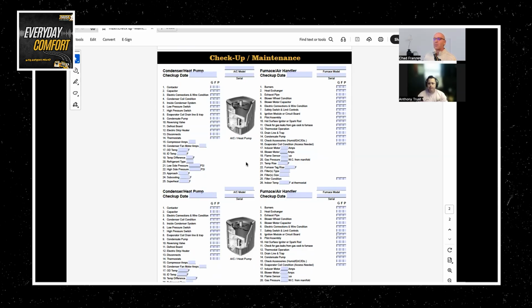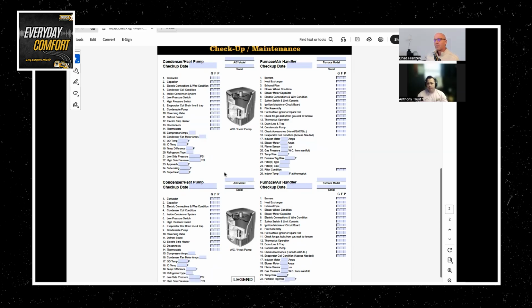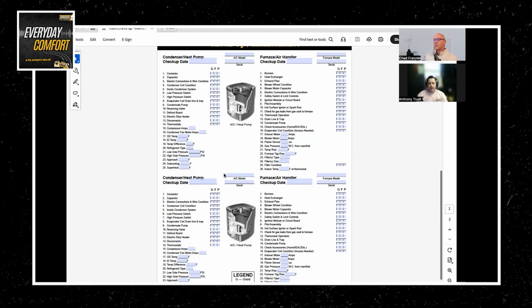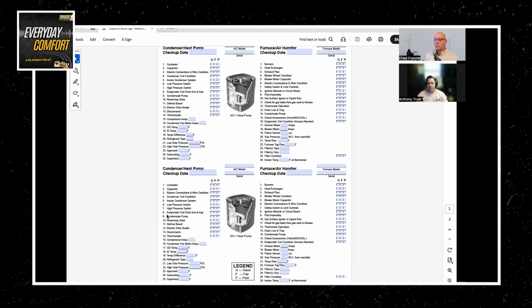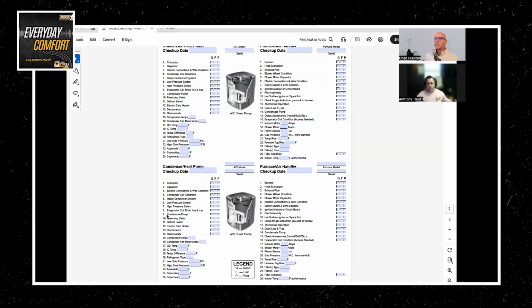Yeah. Like you also measure temperature difference between return and supply air. What does that tell you about system performance? Yeah. So if the motor in the furnace or air handler, or whatever you have, is not blowing enough air across, one, your coils can freeze up, and two, you might have a restriction somewhere. So either in the refrigerant system there's a restriction, or maybe vents are closed, or you have an issue with your ductwork. Those are all things that we can see from checking the pressure and then the temperature from the supply and return. That's really kind of the heartbeat of the system.